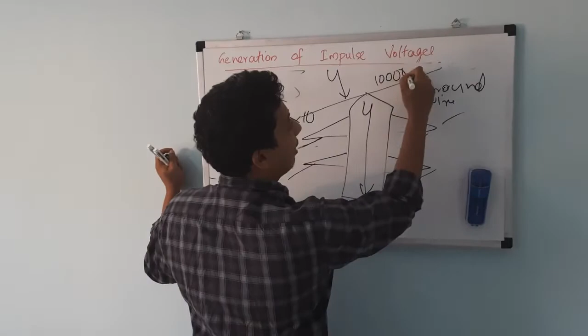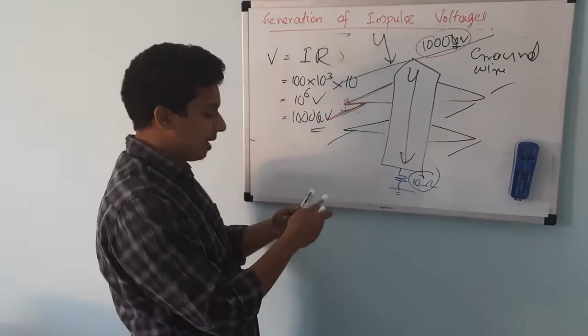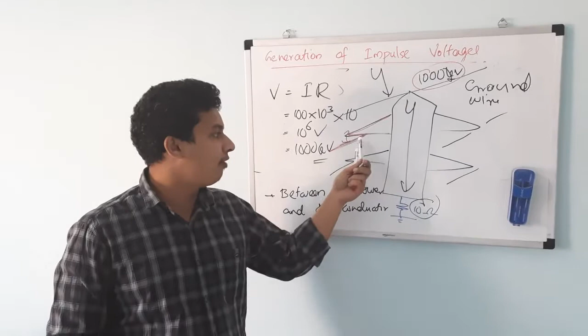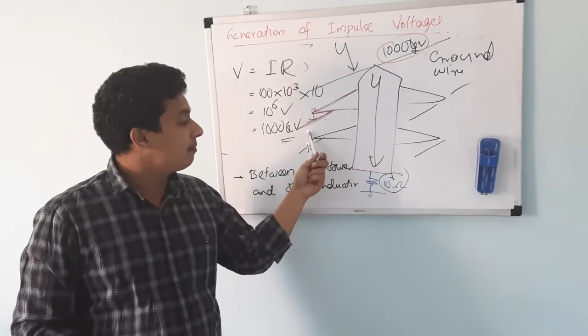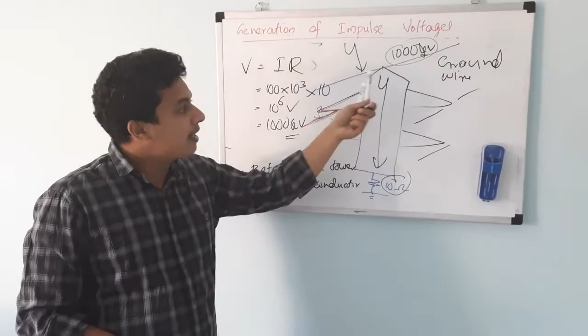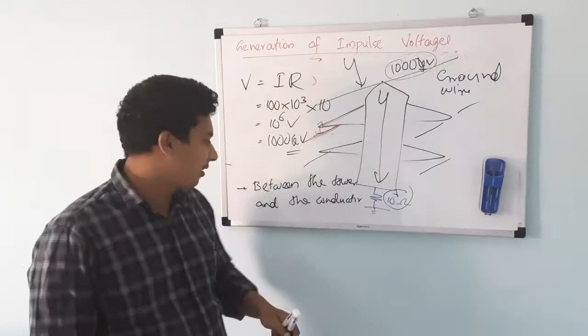Between the tower and the conductor, a flashover can happen, and that is how your impulse voltage exists. Usually, if an over voltage is on the line, flashover occurs from the conductor to the tower. But whenever lightning happens, it is the reverse - it happens from the tower to the conductor. That is the main difference when it comes to lightning, and that is how our lightning impulse happens between the tower and the conductor.